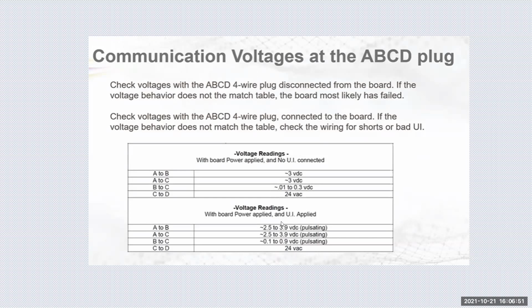But with that being said, now we plug back in. We should be getting 2.5 to 4 volts fluctuating DC voltage plugged back into our unit. Now you go up to your UI, you want your 3.5 volts up at your UI. 3.5 is the number we're using. It's not always going to be that, but you want that up at your UI. If you're getting it up to your UI and you're still having problems, start looking at your UI as being an issue.